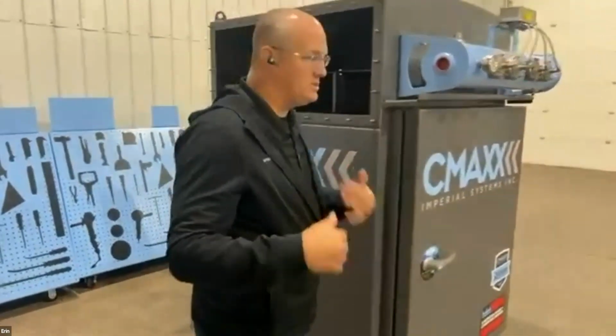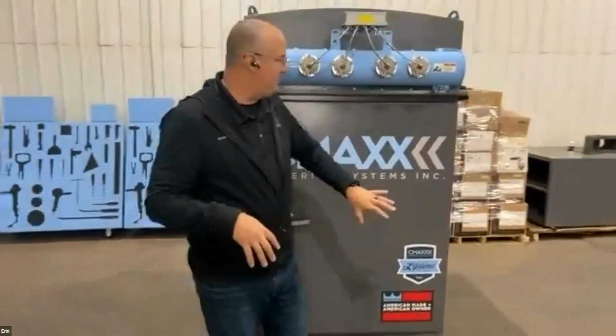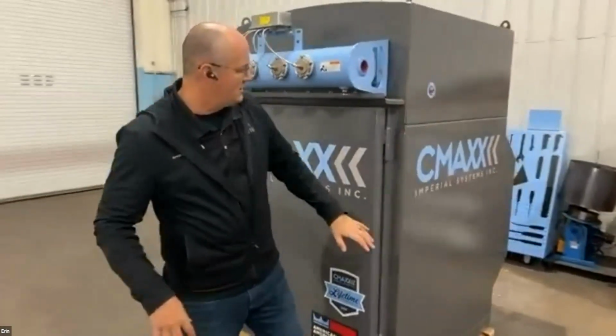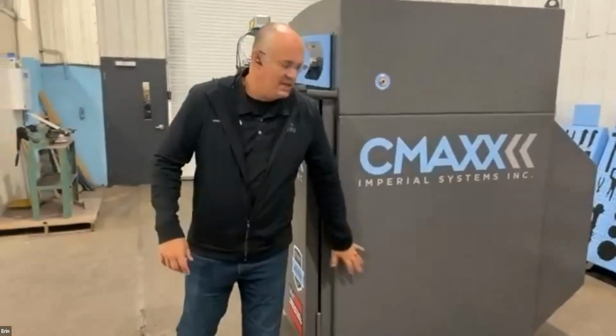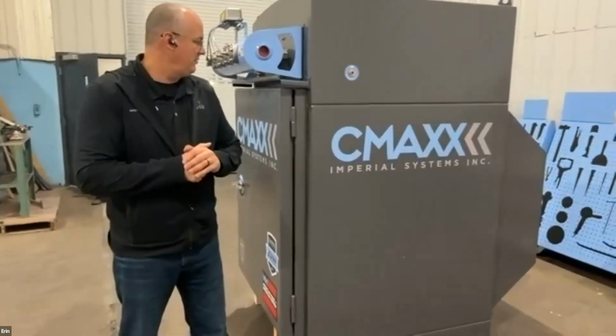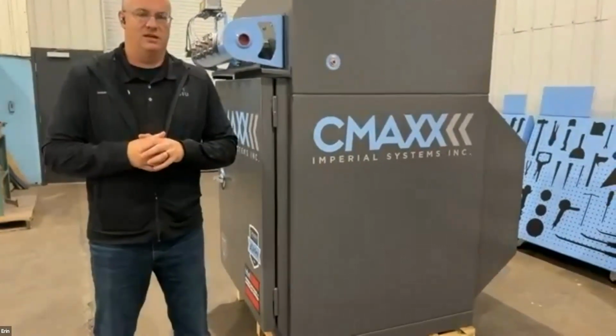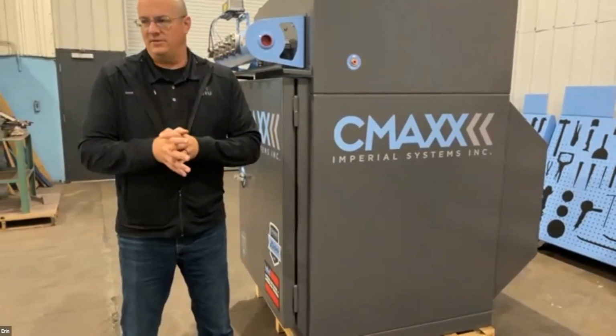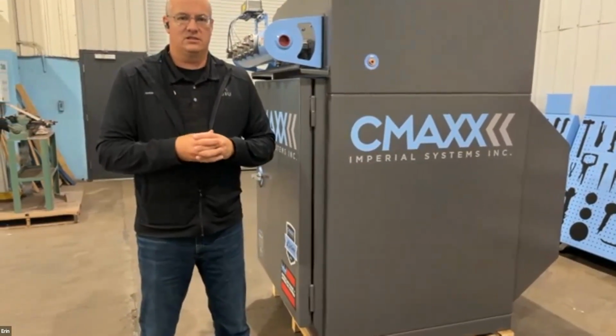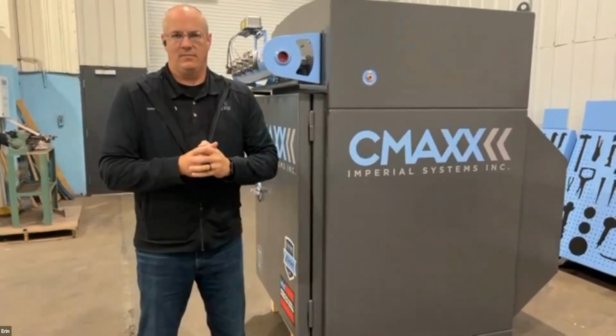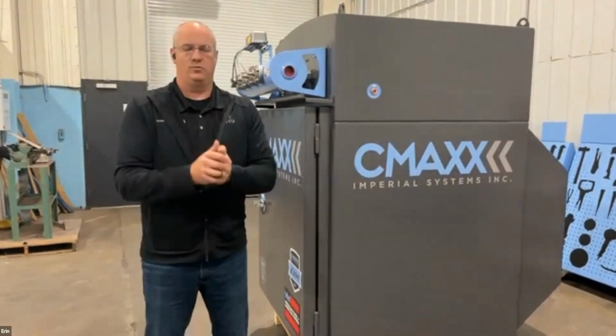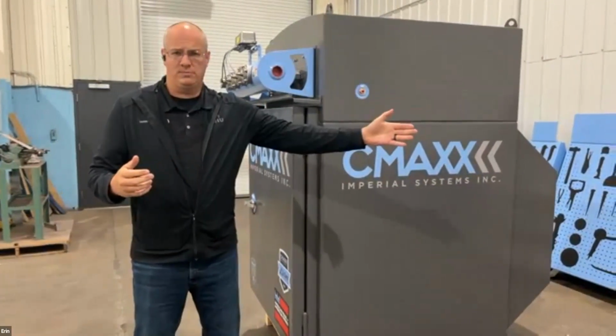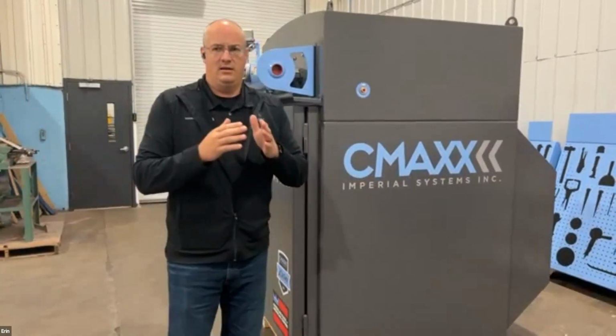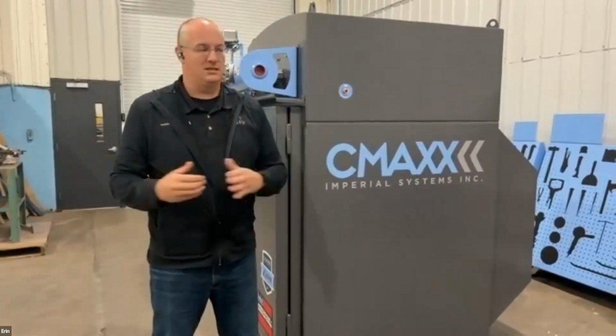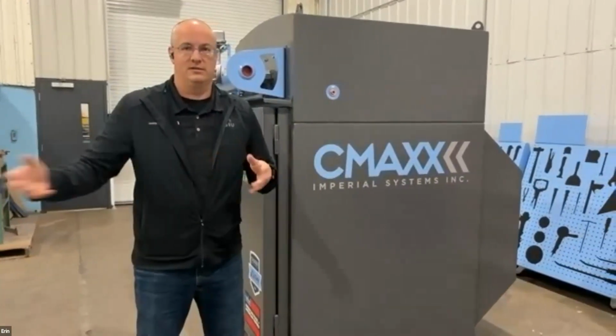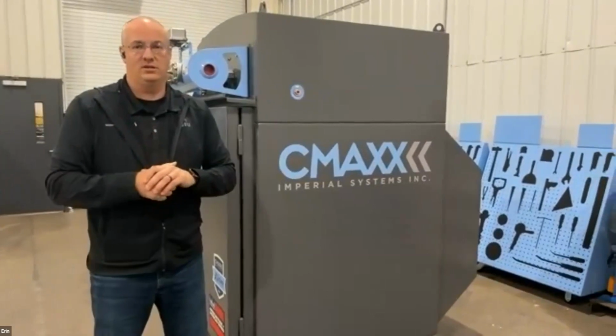So just walking around here, this one does not have an explosion vent on it. If we did have an explosion vent on this collector, it would most likely be on this side of the collector. And like Dave was talking about earlier, that is just an important prevention device for when you get into those explosive dusts. And those are tricky. Dave talked about this also, about how you know when dust is explosive. One of the examples I always like to talk about is wood dust. Wood dust is an explosive dust. We know that. But there's a 2x4 that won't explode, and there's sawdust that will explode. And to know where you're at on that spectrum, you have to get it tested, because you're either closer to a 2x4 or you're closer to sawdust. And so that's just an important thing to take into consideration.